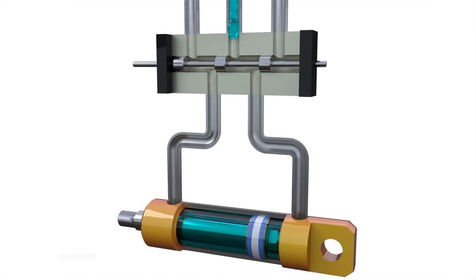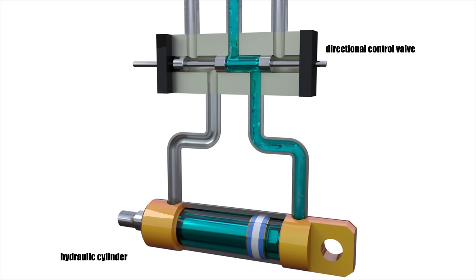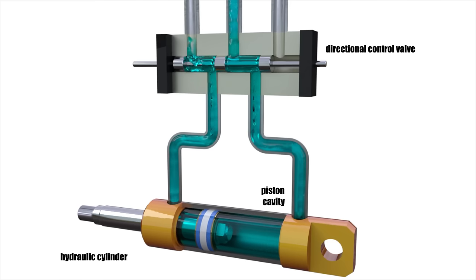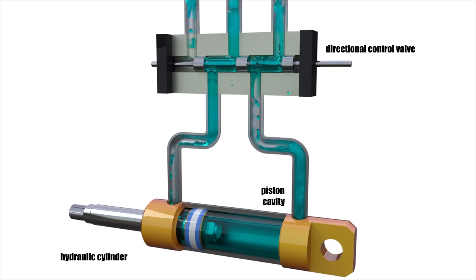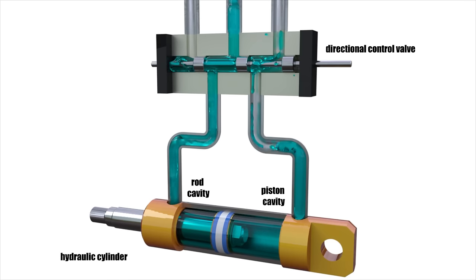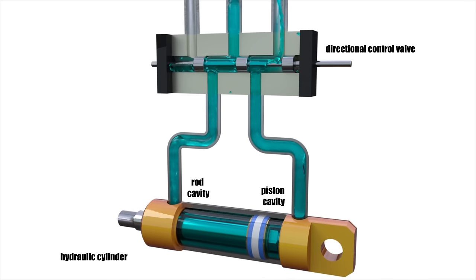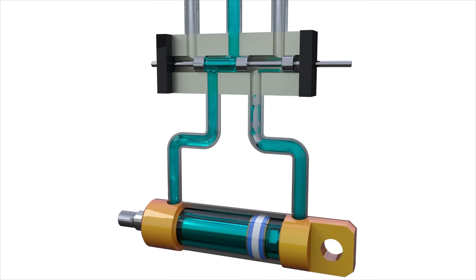In order for a rod of the hydraulic cylinder to start moving forward, it's necessary to direct liquid from the pump into the piston cavity. To push the rod back, it's necessary to direct liquid from the pump into the opposite cavity, the rod one, and allow the liquid from the piston cavity to flow freely into the tank. It turns out that you need to change the routes for the liquid and direct it to different channels.